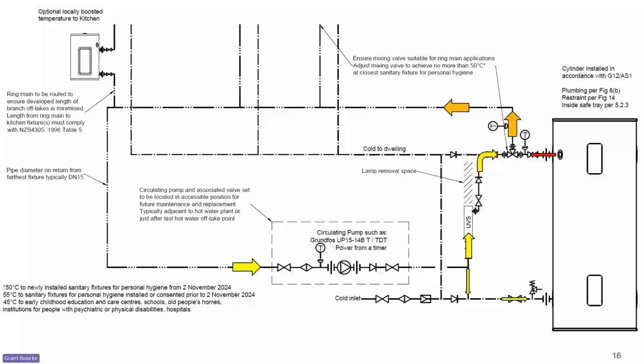Now, this is a concept that's a little bit hard to grasp. I know when I was a young engineer, I struggled to get my head around this a bit, but this is what allows the system to keep circulating when nobody's got a tap on, but keep circulating it at the temperature that we want it to circulate at, not circulate at some higher temperature. So it's really important that we have this bypass leg that goes back to the cold side of the mixing valve.